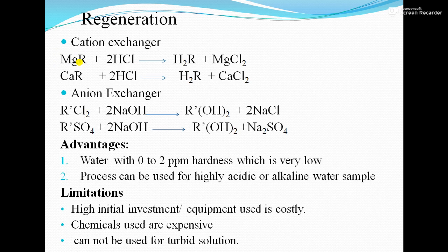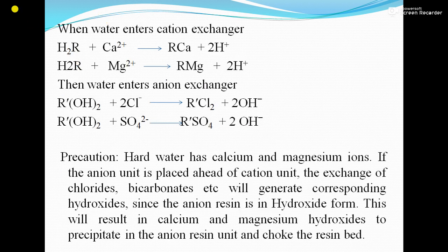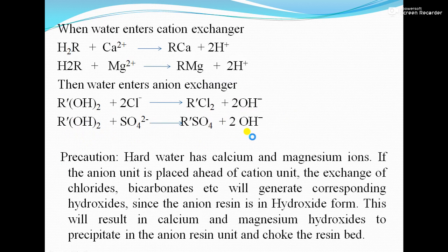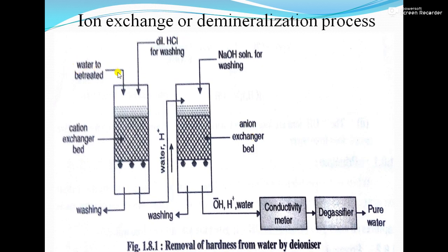For regeneration, after the cation exchanger bed and the anion bed are exhausted, they can be regenerated by dilute HCl and dilute NaOH. MgR on reaction with HCl produces H₂R and magnesium chloride. Similarly, CaR produces H₂R and calcium chloride. RCl₂ on reaction with NaOH gives R(OH)₂ and NaCl. Similarly, R(SO₄) gives R(OH)₂ and sodium sulfate. The diagram shows the softening process and regeneration using dilute HCl with washing, and dilute NaOH with washing.